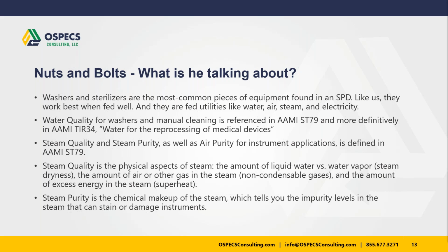So you've got to feed them right. That means washers need to have water. They should have what's called critical water, which is either RO or DI water, preferably, for your final rinse. You need compressed air. You need good quality steam. I'm going to talk more about that in a minute. And you need good quality electricity. Sometimes the electrical systems are noisy. Sometimes the voltage droops and things stop working. There are a number of things that have to be looked at when you're trying to make sure that things are going to be in a situation where they can perform the way they're supposed to.